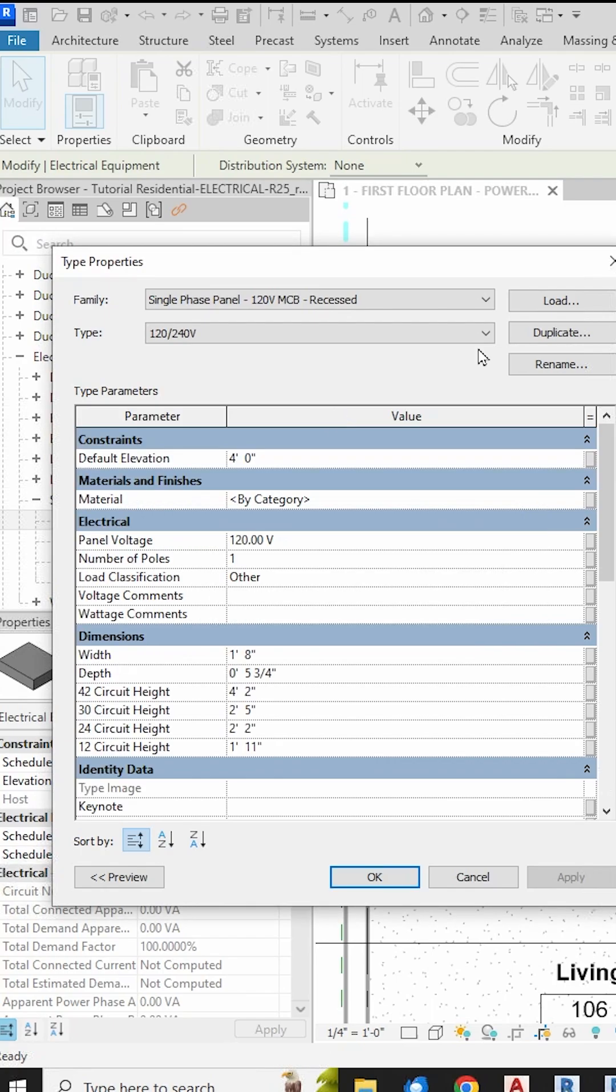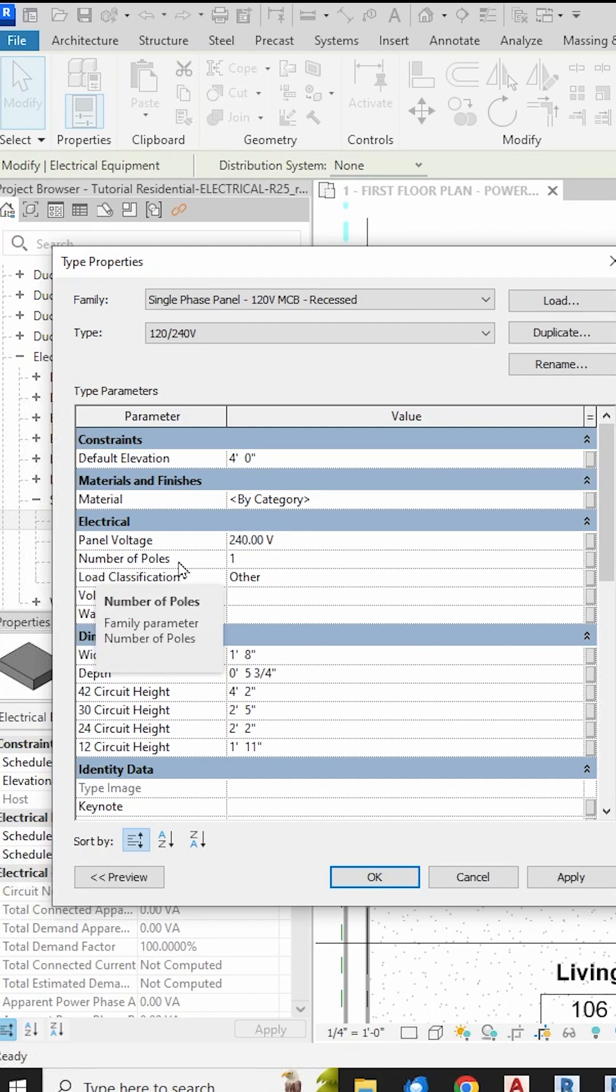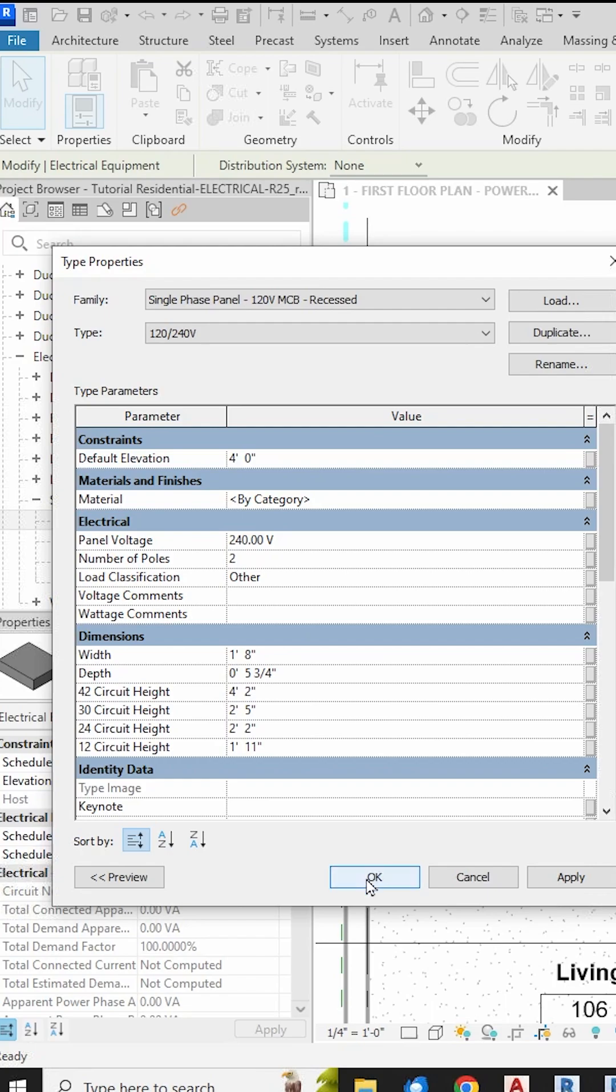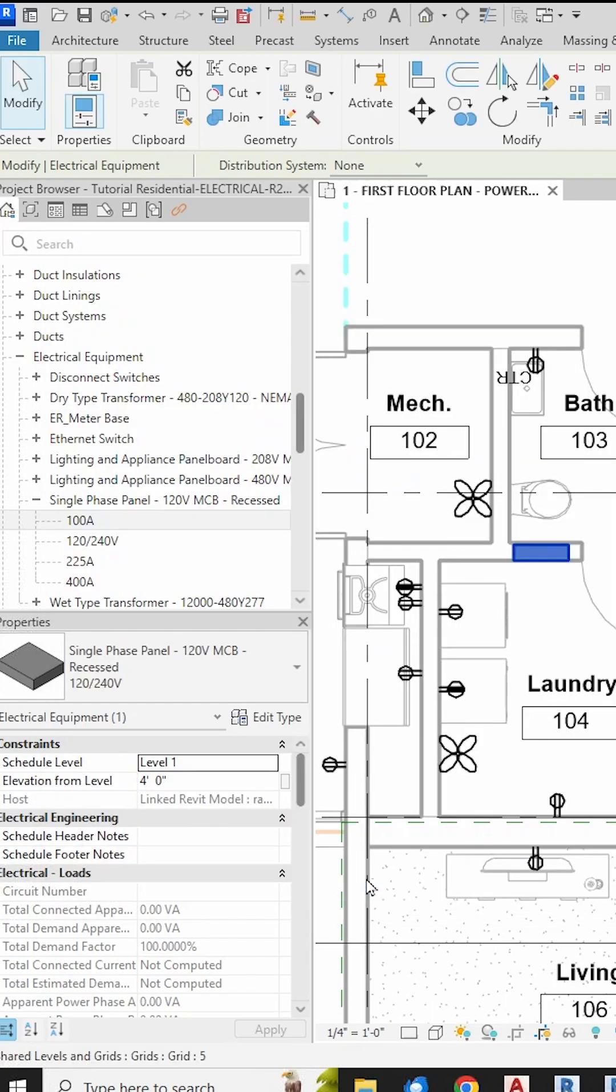I want to create a new type called 120/240, so I hit Duplicate and name it as such. And here we see a parameter for voltage is set to 120 volt. We want to change this to 240 volt. Then we also see that the poles are set to only one. We want to change this to two for 240 volt line to line. Close this out and we're done fixing the panel.